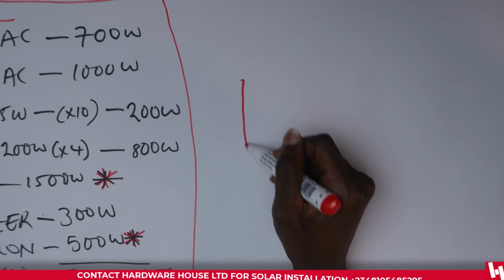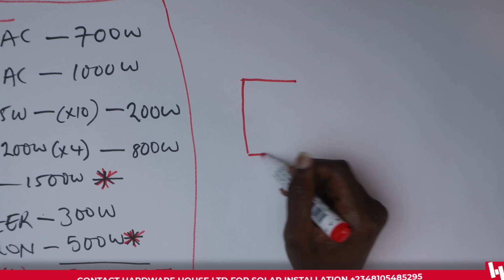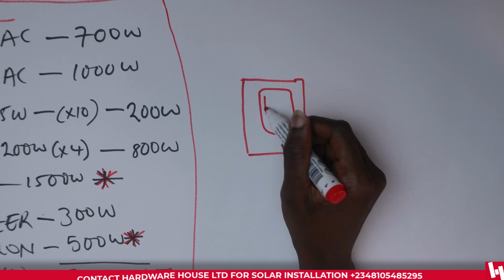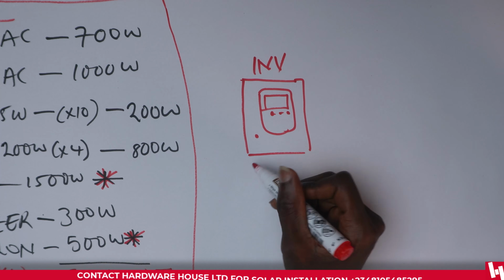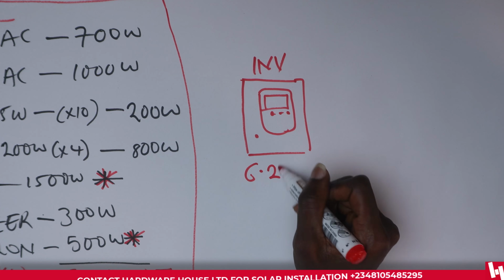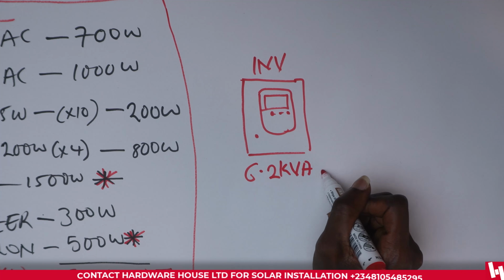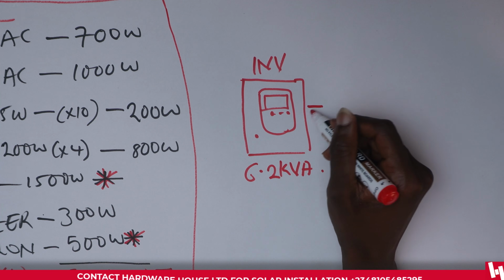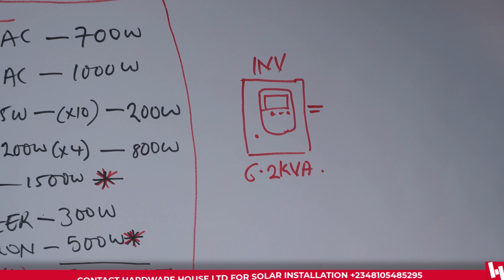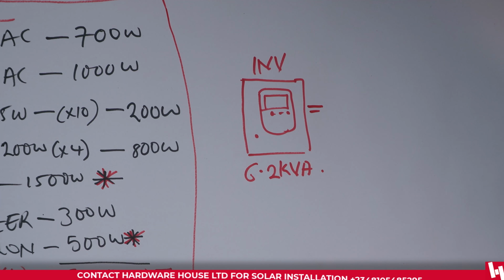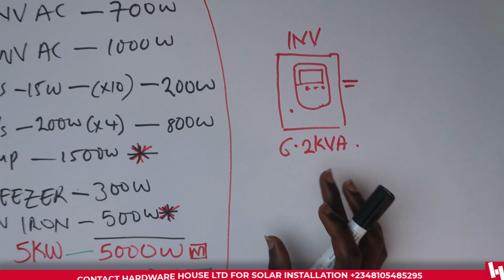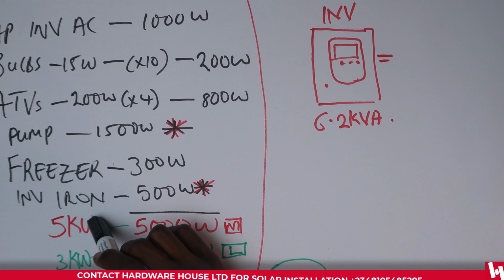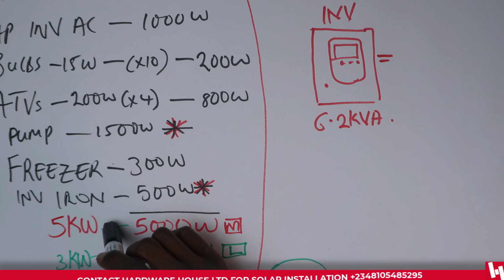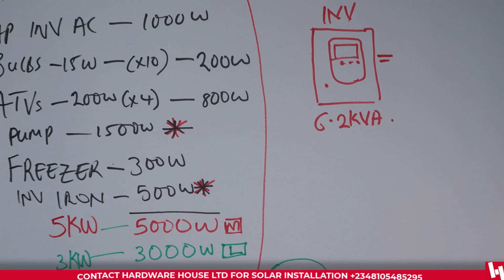So we've figured out the inverter needed, which is a 6.2 kVA inverter. Next is to figure out the battery. So this client told us he doesn't want to carry much load, he doesn't want to overload the system, he only wants the basics of his house to be running, which are the things we listed here. So the inverter would not always be doing this 5 kilowatts all the time.